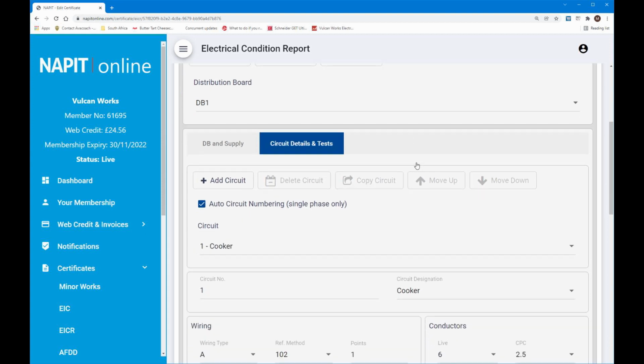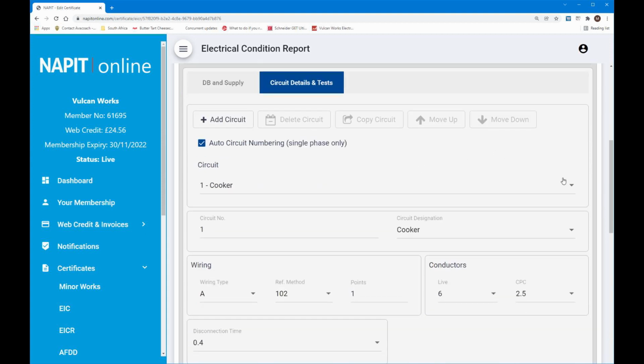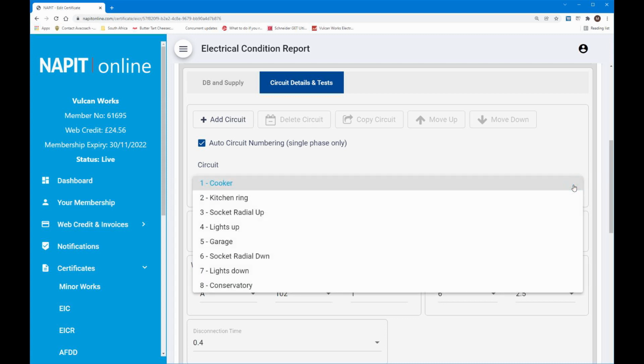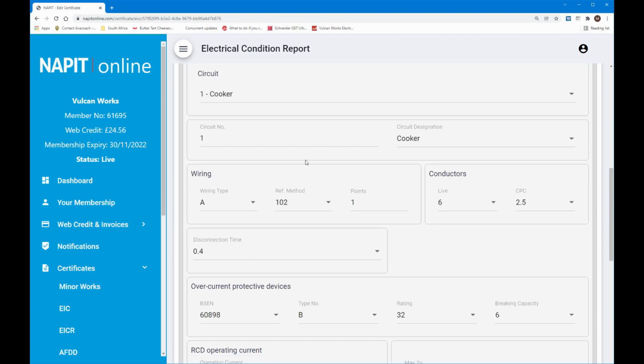So I will drop this down and you'll see there are all the circuits that we're testing. So we're doing a cooker, the kitchen ring, the socket radial upstairs, the lights upstairs, the garage, the socket radial downstairs, the lights downstairs and the conservatory. Now these four, 1, 2, 3, 4, are on one RCD, and these four are on the other RCD. So let's go down and see what we've filled in.